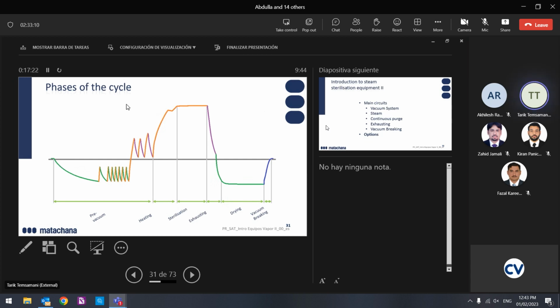The difference between the 121 degree cycle and the 134 degree cycle is the pressure here and the time, the duration. But the number of pulses is the same. We reach the same pressure here: 15 kilopascal and here 70 kilopascal. In the 121 degree cycle we have to reach 121 degrees, 200 kilopascal, and in 134 we have to reach 300 kilopascal, 134 degrees. And then the sterilization time is not the same.